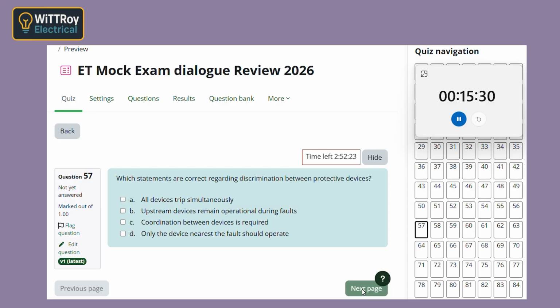That is why upstream devices remain operational during faults is correct, in the sense that they should not trip for a downstream fault if discrimination is correct. And coordination between devices is required. Exactly. Discrimination doesn't happen by luck. Ratings and characteristics must be selected properly. All devices trip simultaneously is the opposite of good discrimination.